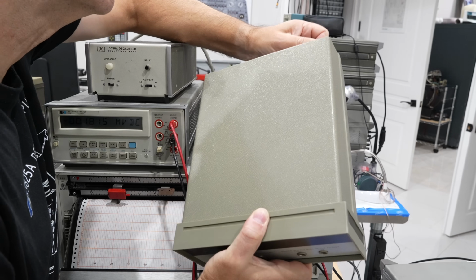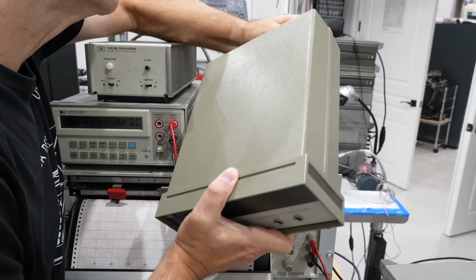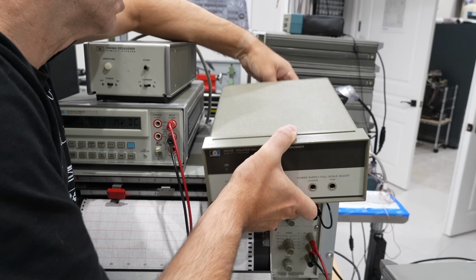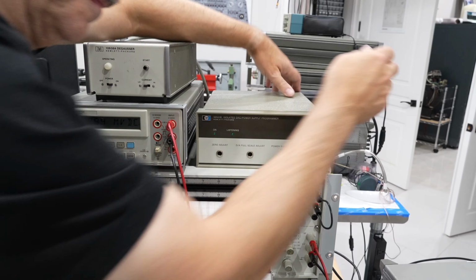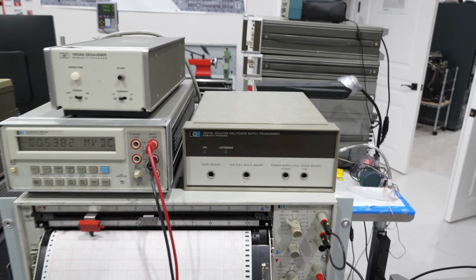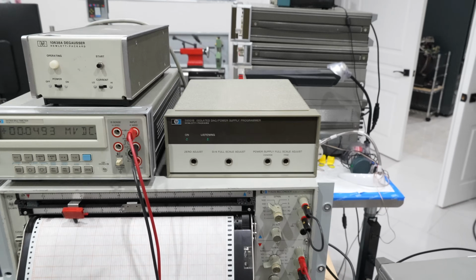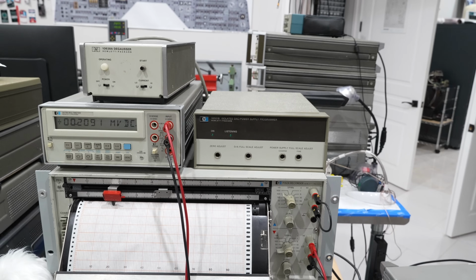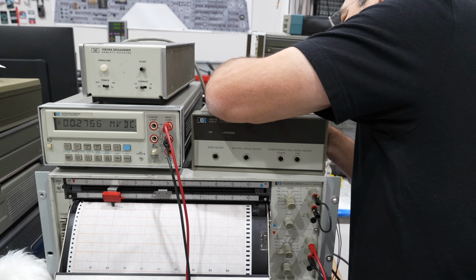So this handy dandy unit had become inaccurate because of a dirty switch. But once repaired, it's back to the old HP goodness, exceeding its spec by a factor of 10 after 40 years. No Chinese instrument, this one. So in the atomic clock metrology setup it goes, and it's time to look at the other problematic unit, which I bet you has the exact same fault.